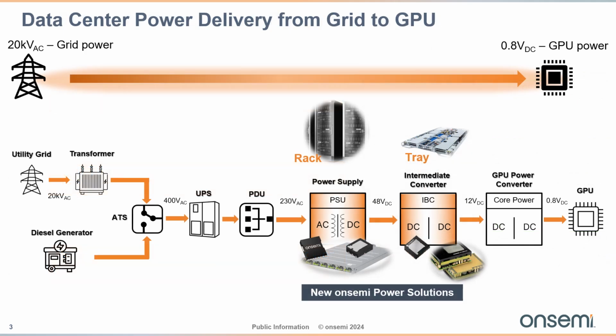Often data centers are powered from the 20 kilovolt medium voltage transmission line. Power delivery to the GPU rack goes through many power conversions. Power first goes through a traditional transformer and an automated switch control, which is backed up by a diesel generator. By now, the 20 kilovolt line is converted to a 3-phase 400 volt AC. It then goes through a UPS with a battery storage capacity, aiding the diesel generator during power outages. And then the power distribution unit converts the 3-phase 400 volt AC to a single-phase 230 volt AC line at the rack level. At the rack, where the GPU servers are located, rest of the power conversion happens.